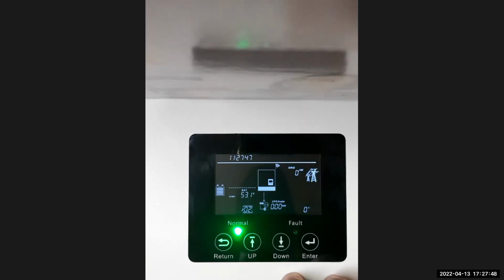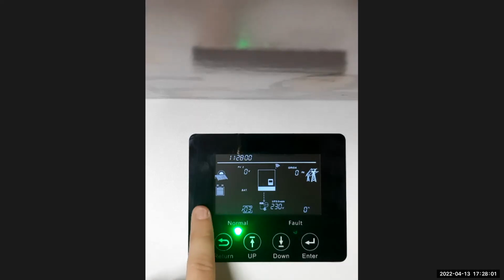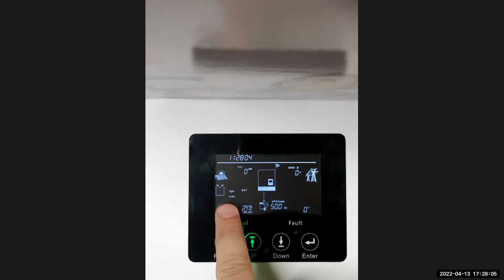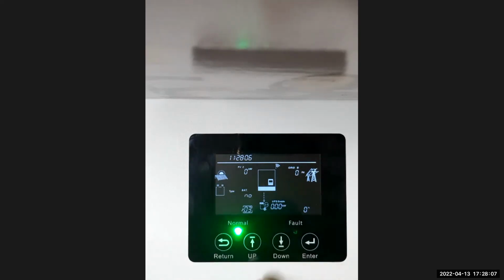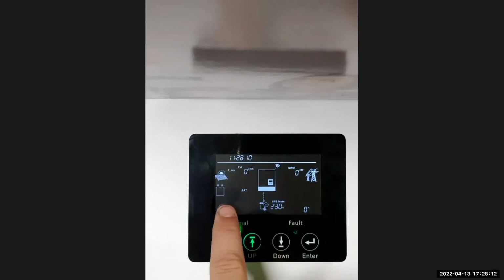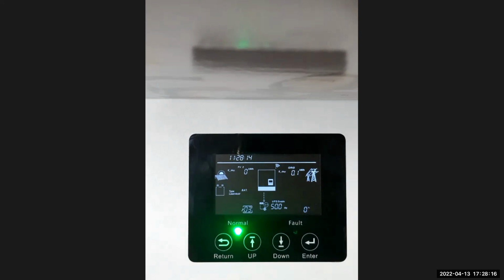So on setting 2, we've already done the panels. Now, number 3. This is one of the first settings that you'll be able to start to adjust. So number 3 means this is the battery settings. Now, you can enter number 3, then you see the type that's flashing. Here you can decide which type of battery you're using. So the type flashing now is lead acid. That's the same as user.